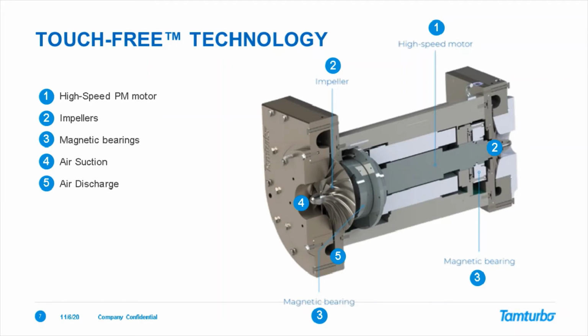The first commercial application was launched in 1976, and it actually originated already after the Second World War for uranium enrichment, also for centrifuges. And it has been used successfully, for example, in low pressure wastewater aeration compressors or blowers, already for decades, with units in the field for more than 25 years, with practically no maintenance during the life cycle of the product. And this is actually the same technology, and the same motors, that are used when there's a gas pocket under the sea, and you want to lower a motor there to pump the natural gas out of the seabed. You don't want to go there every 4,000 hours to change the oils or do maintenance on the unit.